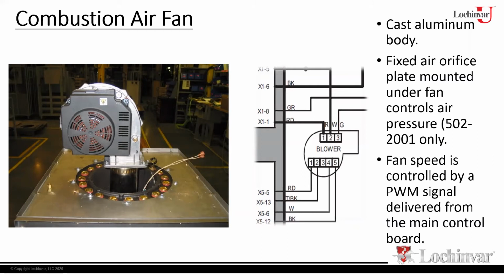Now, as I mentioned, we're monitoring the feedback. So if the fan speed is out of range for whatever reason, we're going to go into a lockout. So when we get this call, fan speed lockout issues, you're primarily dealing with three possible issues: either a fan, a control module, or the wiring. To be completely honest with you, in most cases, it's typically a wiring issue.